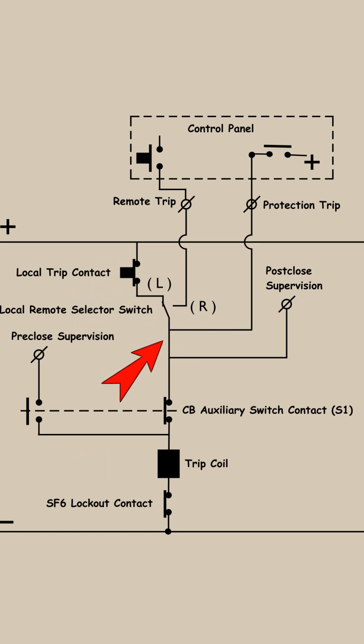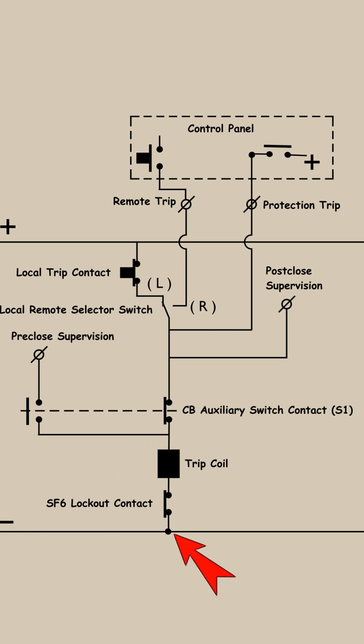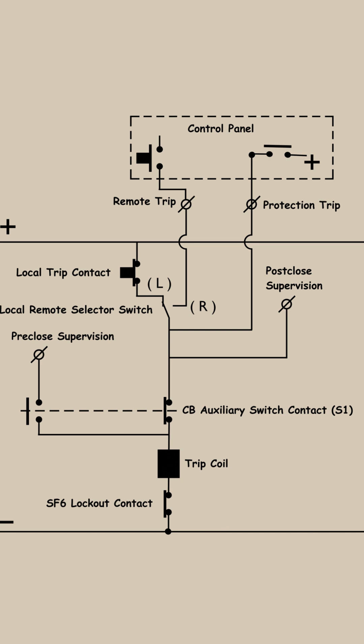Since the SF6 gas is at normal pressure, that contact will be closed, allowing the negative potential to reach the coil terminal. As a result, the coil will be energized and it will trip the circuit breaker.